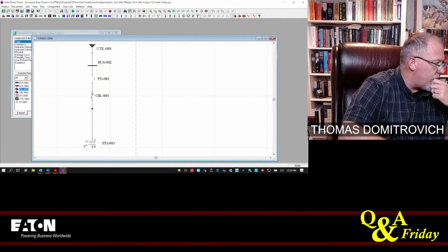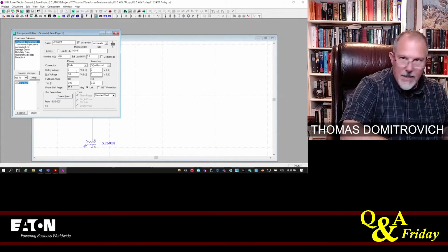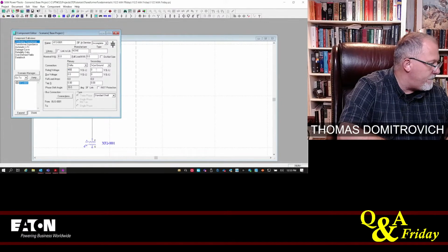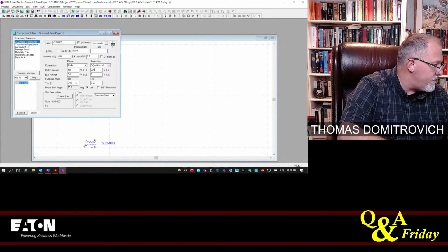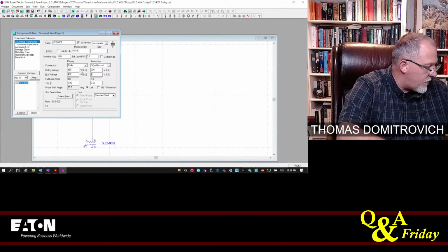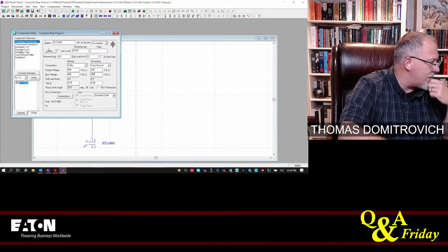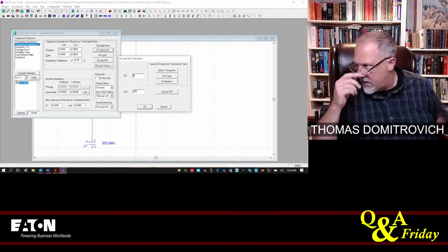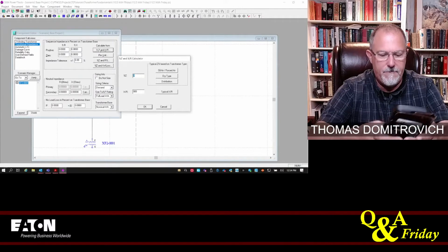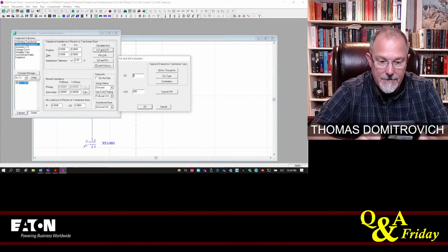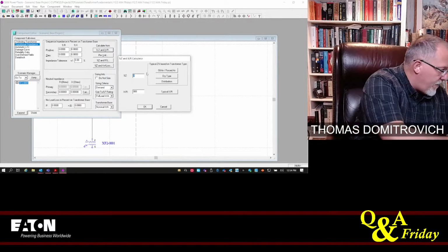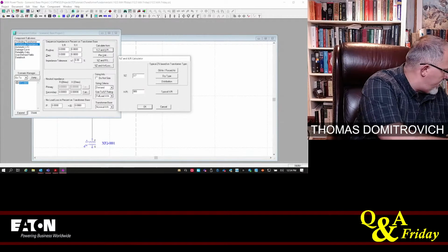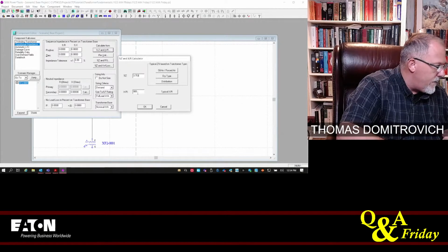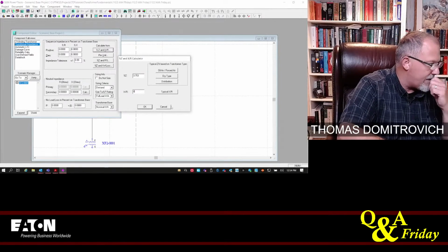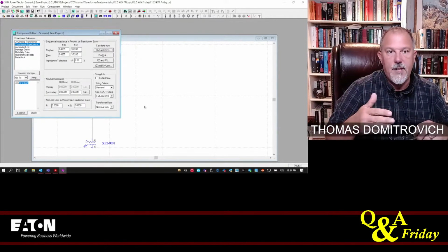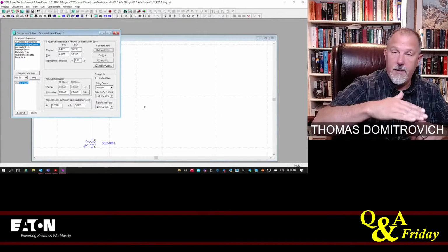All right, so let's start with this transformer. I have a delta Y ground. I got a 480 volt primary. I've got a 208 volt secondary. Bus voltage is 480. Secondary is 208. Transformer impedance. We said transformer impedance was 4.17. So I take 4.17 times 0.9, 3.753, give it an 8, X to R. Why did I do a 0.9? Because plus or minus 10%, maximum available fault current will be at a 0.9. Lower the impedance, higher the fault current.